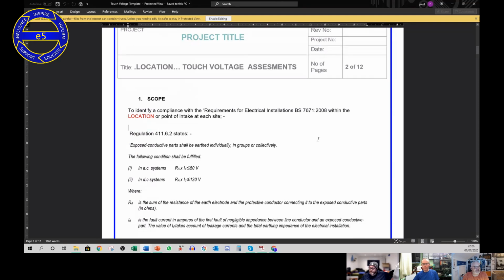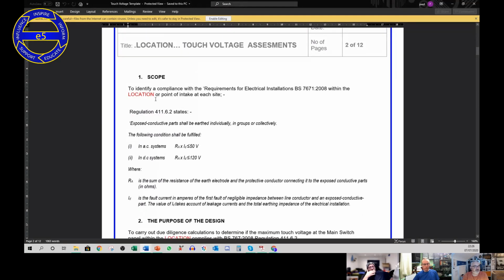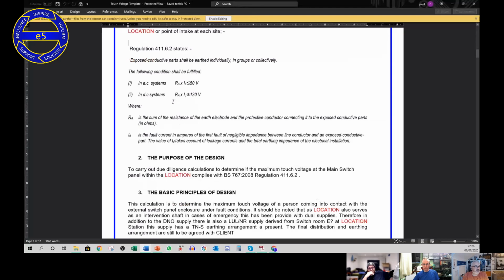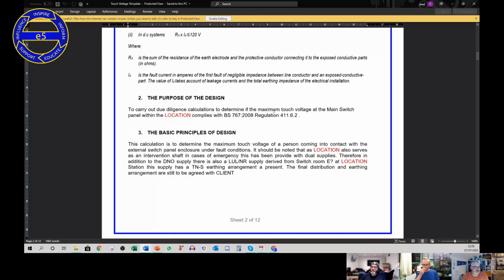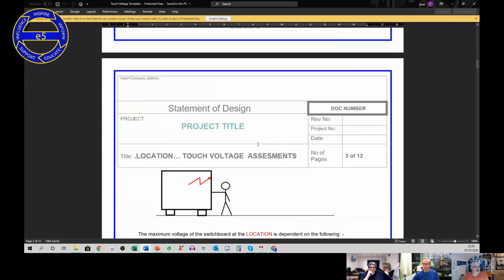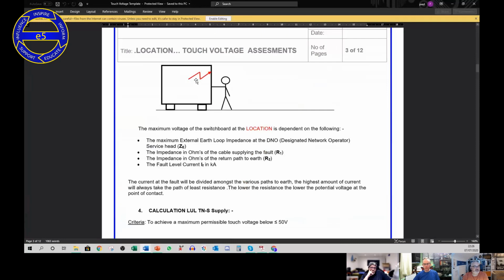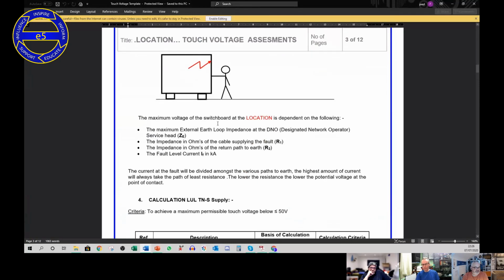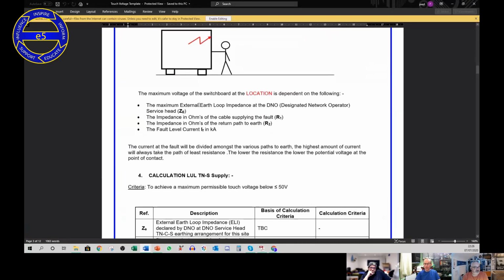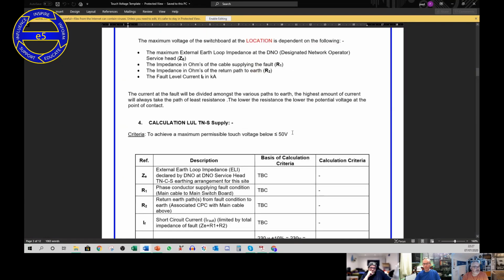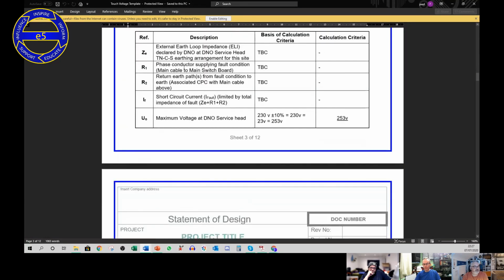So what we did was say, look, this is the scope to identify compliance at a certain location. The purpose of the design was to determine if the maximum touch voltage of the main switch complies with it or not. Then we drew a little box with a potential fault. For anyone who hasn't done this before, the maximum voltage of the switchboard depends on the ZE, the impedance of the cable, R1, R2, and the fault current level in kA. And then we worked out a little formula here.